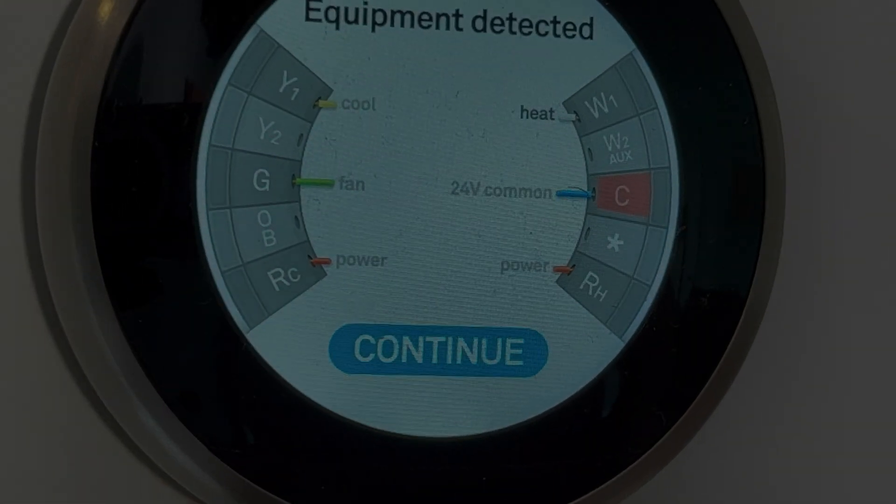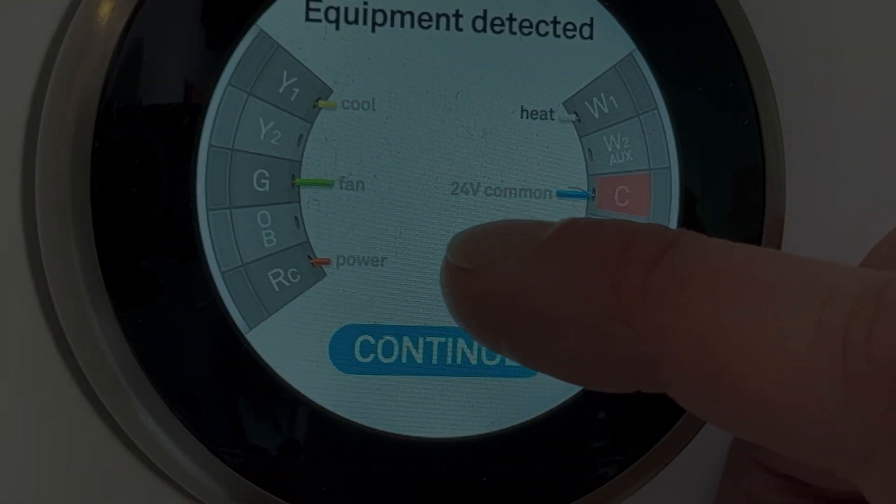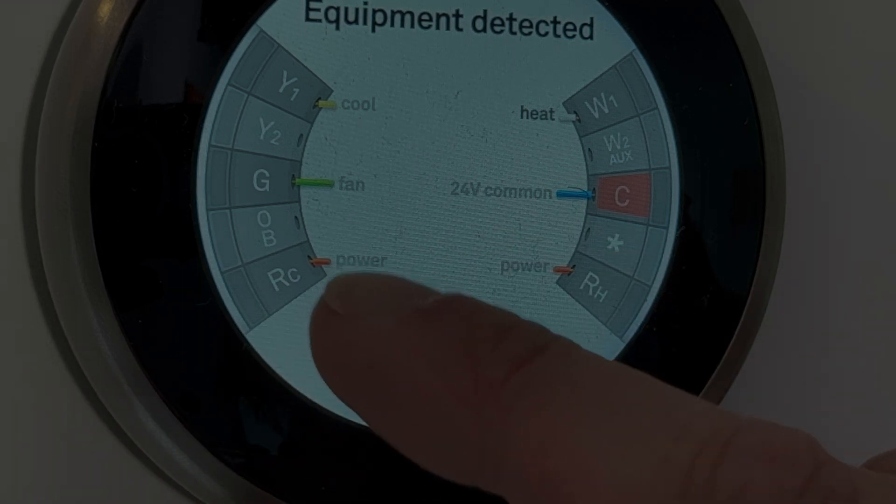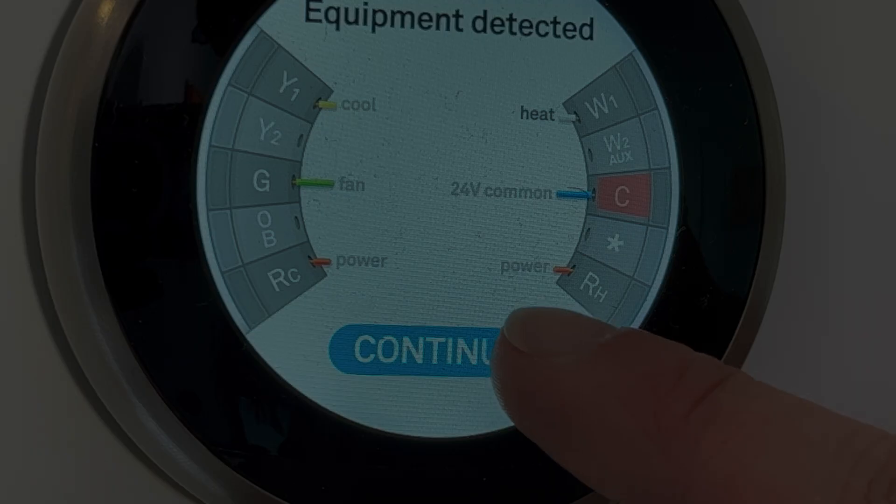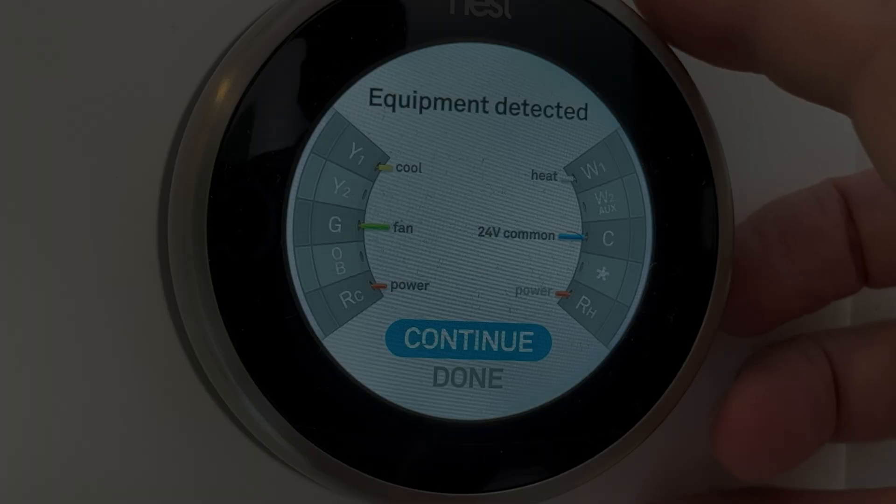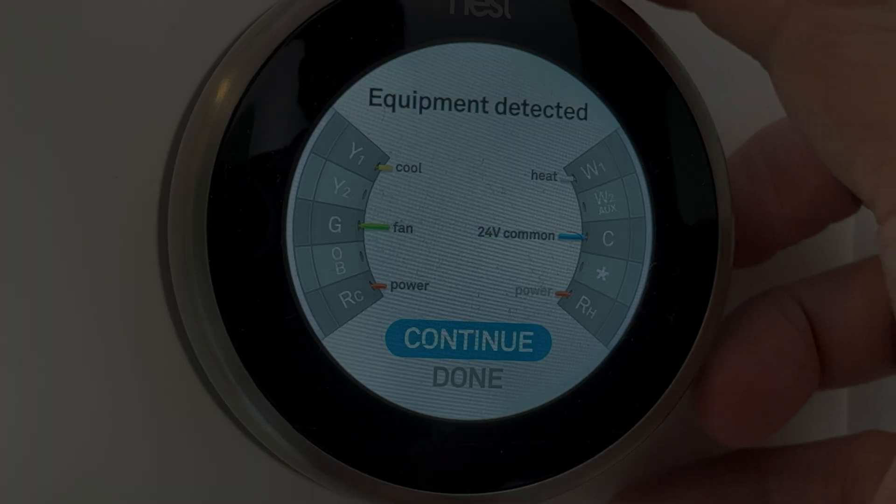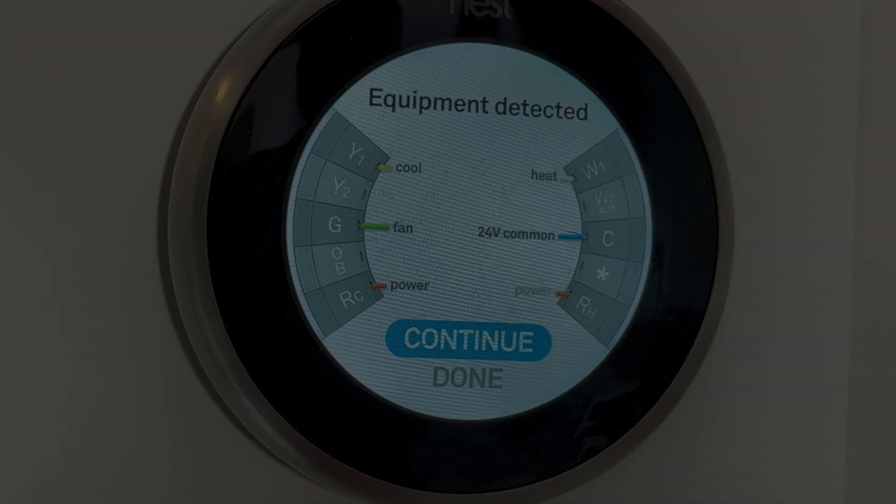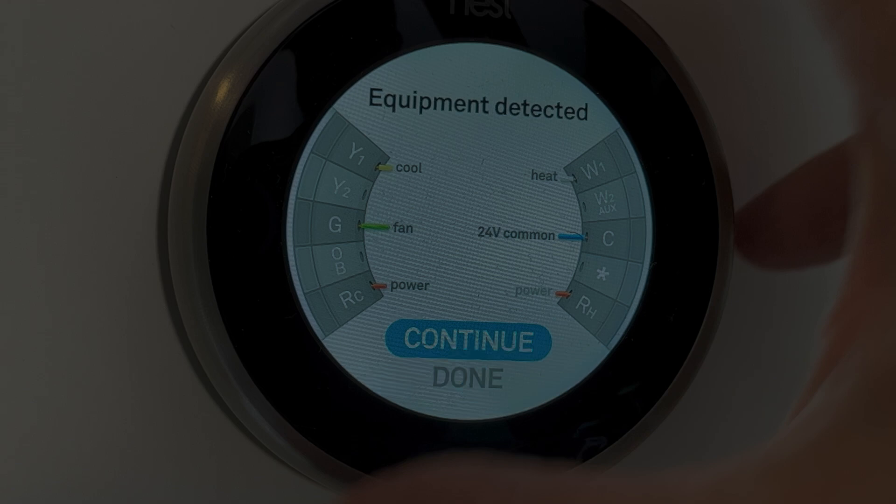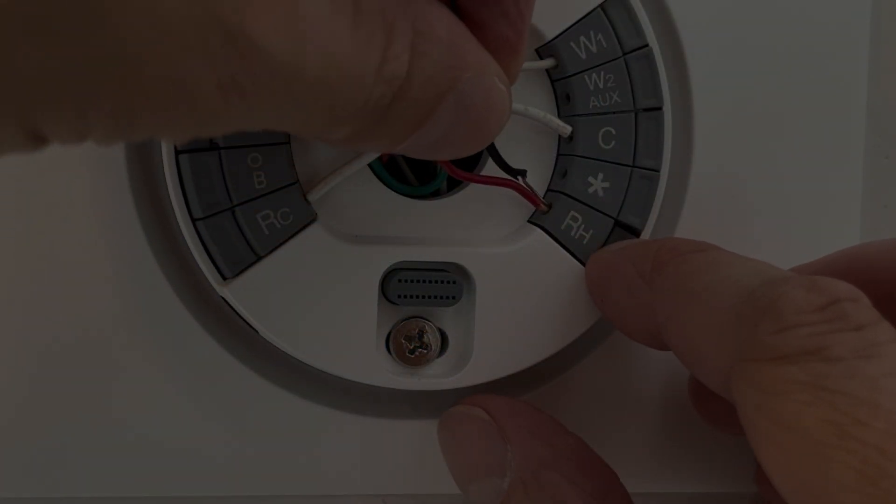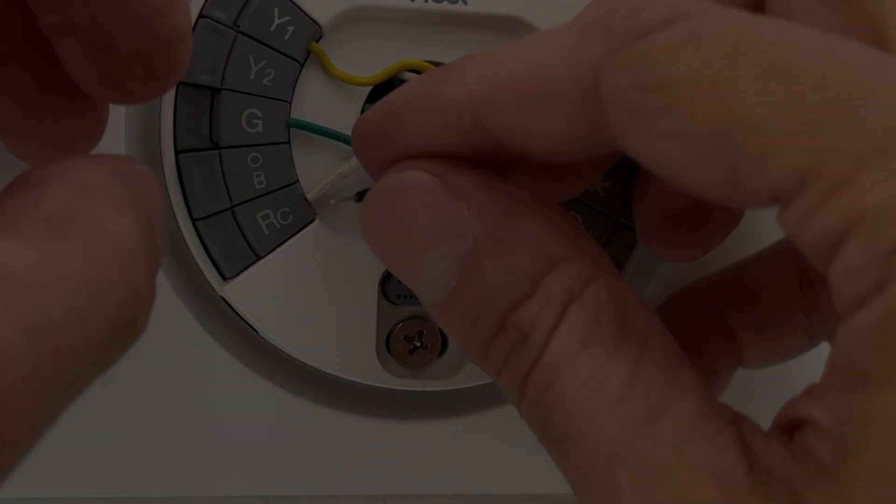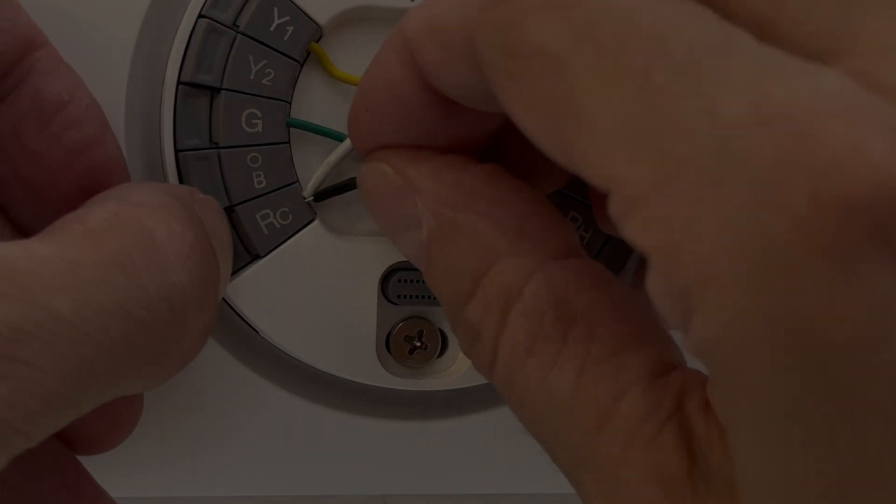So let us check here and have a quick look. We do go to equipment and then we see here already the 24 volts common is in there and also power, but the C is currently marked in red and that's because we haven't actually plugged in our power supply yet. So let's do that really quick. And now we see here the 24 volts common is actually now also in black. The writing is in black as well as the RC power is also in black, but we can see that the RH is actually grayed out. The power is grayed out and that's because we do have a cooling or air conditioning system attached here.